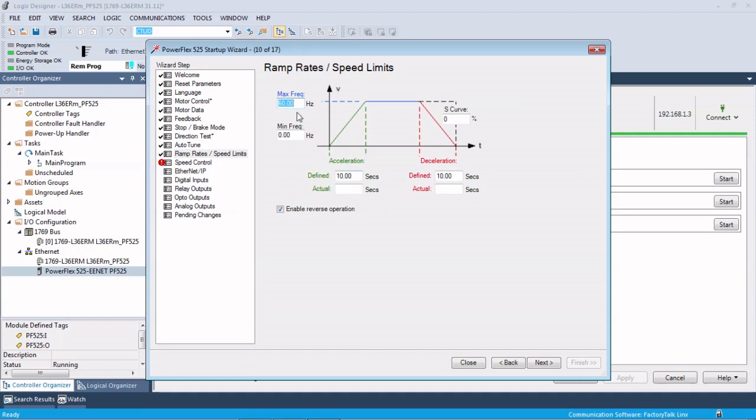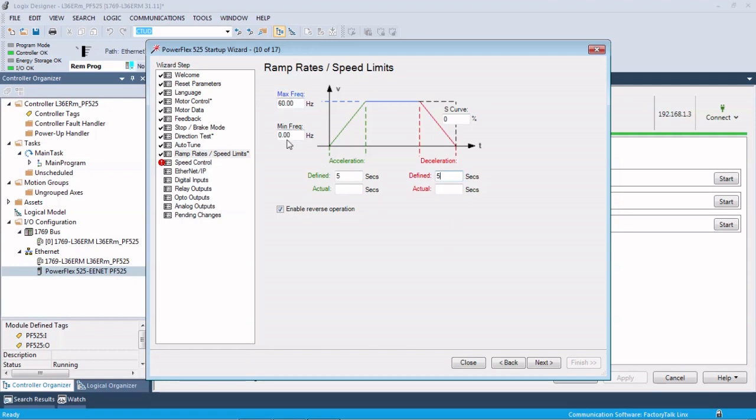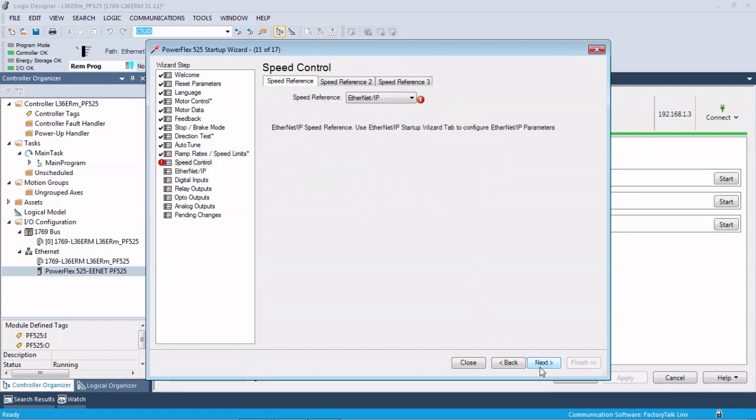Ramp rates. So ramp rates, 0 to 60 hertz, right? And then acceleration and deceleration. So this nice little trapezoid graphic here to show you what they're trying to get out of it. We're just going to change these to 5 seconds. 0 to 60 is fine. And if you wanted an S-curve for more of a smooth acceleration and deceleration, you could do that as well.